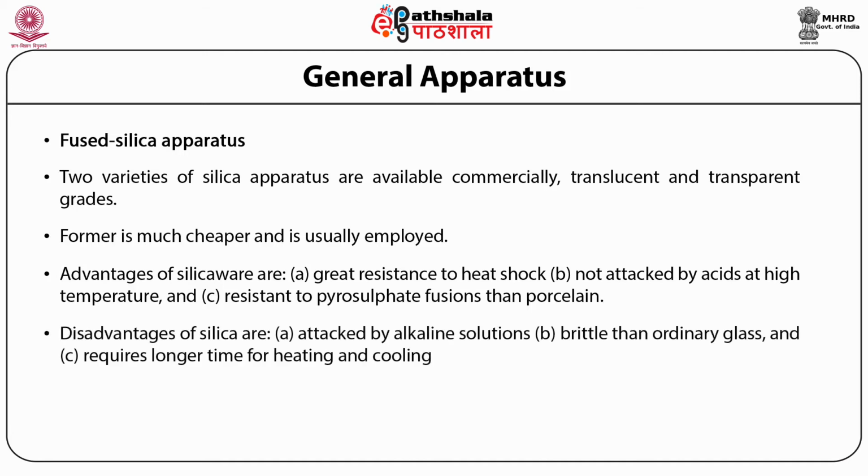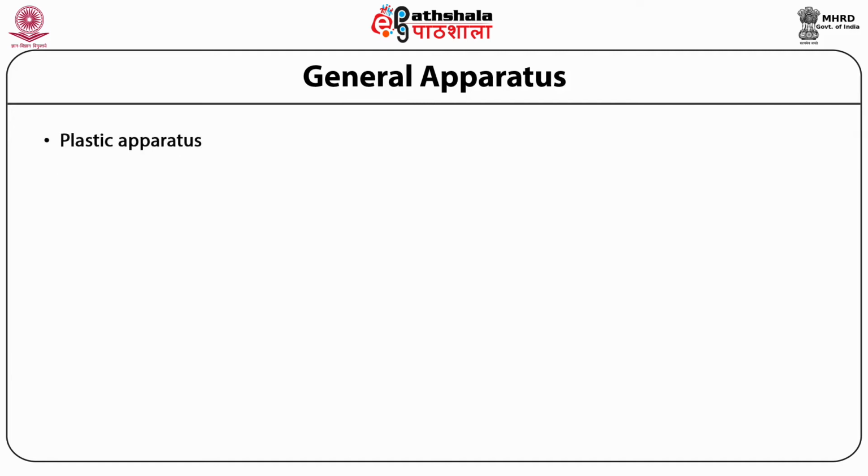The chief disadvantages of silica are that it is attacked by alkaline solutions and particularly by fused alkalis and carbonates. It is more brittle than ordinary glass and it requires a much longer time for heating and cooling than does, say, platinum apparatus.